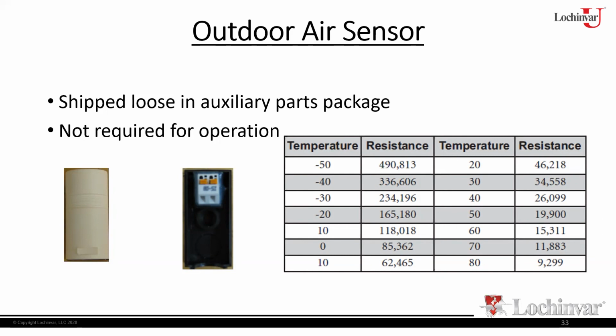But remember, because it's a non-condensing heater, we got to be careful. If it's a non-condensing heater in an application where those water temperatures can drop below 130 degrees, we want to put this caveat in here: because it's non-condensing, I don't want that inlet temperature dropping below 130 degrees. If it does, then we're going to condense on the heat exchanger, which would be bad. So in this case, if we're going to use a reset schedule, we do want to make sure we put some sort of low temp protection on the boiler, i.e. through a mixing valve, the low temp valve, whatever, and pipe it in that way. There's instructions in the manual for that. So I did want to throw that in there. If you use an outdoor air sensor, you're more than likely going to reset your schedule. The temperature is going to drop fairly low for your system, but we will still want to keep that temperature at the boiler above 130 degrees coming back so we don't condense on the heat exchanger. If you're condensing on the heat exchanger, that'll be real easy to see. You'll get this nice green patina on the heat exchanger, or if you get soot buildup on the heat exchanger, it's generally a good indication that you're condensing.